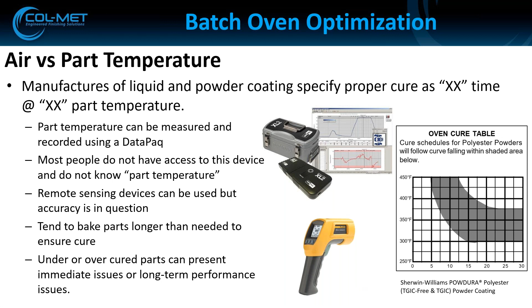So our solution to that, which we released this year, is Smart Batch, and it's an optional upgrade to the controls. What it does is use magnetic thermocouples inside the oven, and they plug into a junction box mounted to the wall on the inside of the oven. That's convenient because if you don't need the probes during the day, you can disconnect them and not have to cycle through the heat. Also, you're not having to run probes along the floor where it's a trip hazard or where they could get damaged by a door opening and closing on them.